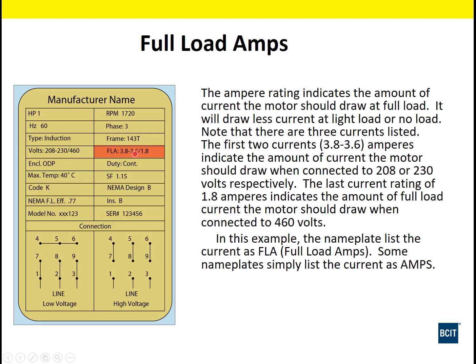And again, here we go, full load amps. To match, we have a range of low voltage amps to match the range of lower voltages. So when we run it at 208 volts, our maximum current to the motor is going to be 3.8. When we're running it at 230 volts, the maximum current the motor is going to draw is 3.6. And then 460 volts at the high voltage connection will be 1.8. Now, that's the current the motor is going to draw when it's running at 1720 RPM and putting out 1 horsepower of work.